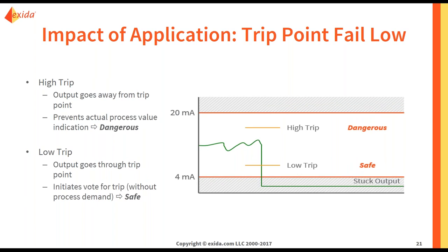What about trip point fail low? If you have a high trip, the output goes away from the trip point. It is preventing measurement of the actual process value, and it is not tripping your plant, so it is a dangerous failure. However, if you have a low trip, your output is going through the trip point, initiating a trip without a hazard from the system. You are tripping the plant — it is a safe failure.